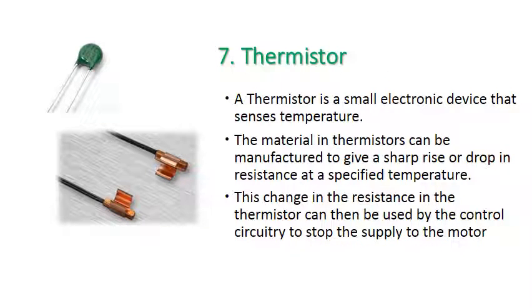So now we'll have a look at thermistors. Now, thermistors are a small electronic device that, like I said, senses temperature. The materials they're made out of give a sharp rise or drop in resistance, depending on which one you have, at a specified temperature. So this change in resistance can be used to control the circuitry, and it might be wired up to a VSD, and the VSD monitors the thermistor. If it sees a change in state, it knows, oh, this motor's hot, and will shut it down.